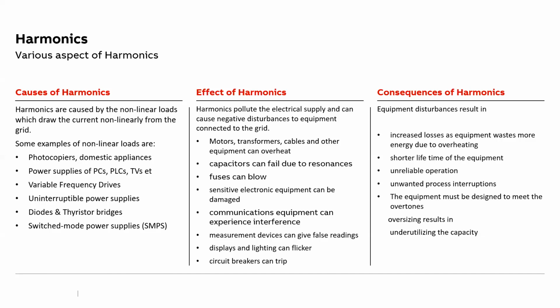Then it causes disturbances in other connected load and sensitive equipment, for example a communication system or measuring devices. It causes flickering and disturbance in the communication systems. If you remember, we talked about mission critical applications like airports and data centers. Here even a slight change matters because there are very sensitive equipments. The ATC control room has the communication system, and the radars are very sensitive. Similarly, in hospitals, the MRI or CT machines are very sensitive. Even slight changes can have a fatal effect. Plus, it affects the measuring equipment and can give false readings. Circuit breakers can trip, fuses can blow. These are the effects of harmonics.